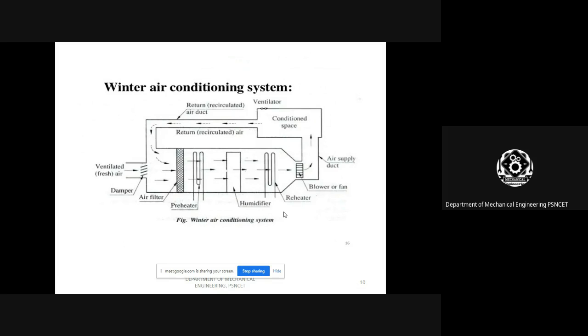You see here, the same things are available: damper, air filter. Here, not a cooling coil, but a preheater coil and a humidifier. With the humidifier, we supply water particles to the air. And then the reheater. This reheater is mainly for human comfort. And this is a blower or fan to supply the air to the conditioned space. Right. Now we see the working principle.